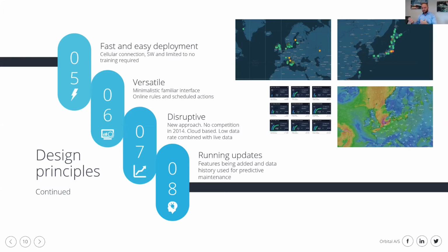We also have the capability, as it's a two-way connection, to control the wind turbines from rules in our SCADA system. So if you have what's called shadowing on a neighbor's house, we could put a calendar into the SCADA system and tell it when it should shut down, and then we would simply have a light sensor, a lumen sensor, sitting on the turbine. So we know if shadowing can happen, and then we can shut down within these times. This makes it possible to add functionality without going to a wind turbine and putting new embedded software into the control system.